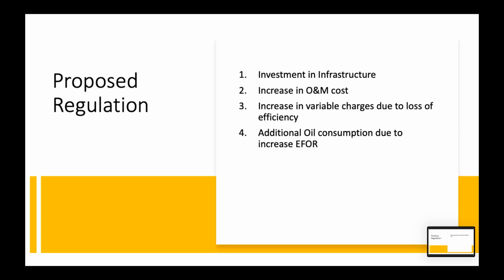In the proposed regulation, the compensation for operation at a technical minimum of 40% is considered on four grounds. The first ground is the investment in infrastructure which is required to sustain operation at 40% load. The second is the increase in the O&M cost, because when the unit has to run at 40% and then go to 100%, there would be cycling losses, valve passings and other things may happen. So there would be an increase in the repair and maintenance cost, and that has been considered in the O&M cost.